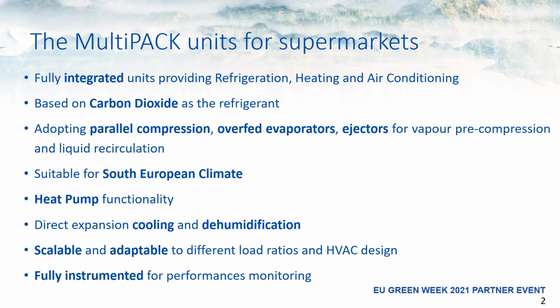It's a fully integrated unit which is able to provide refrigeration, heating and air conditioning. It's based on carbon dioxide as the refrigerant, and it is adopting the state-of-the-art technology, including parallel compression, overfed evaporators, and ejectors for vapor precompression and liquid recirculation. The units developed within MultiPACK are suitable for the South European climate.